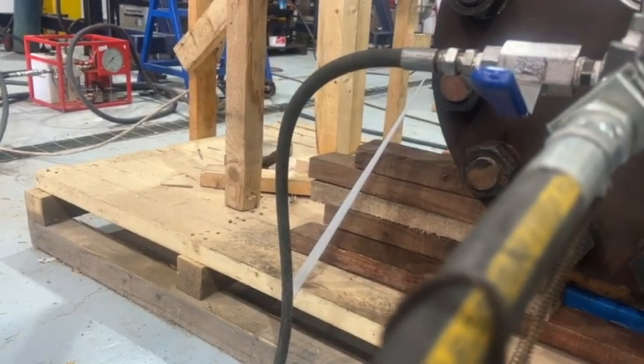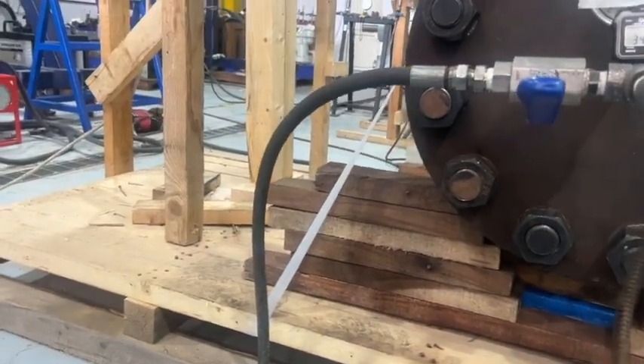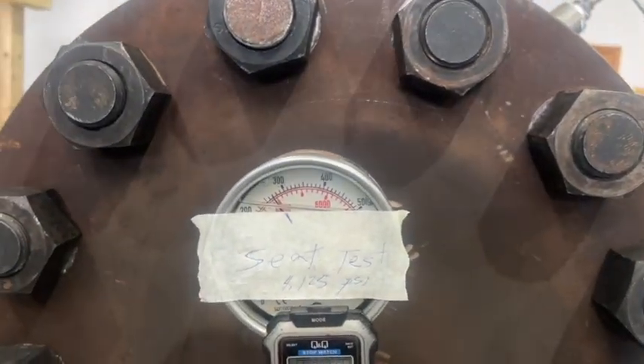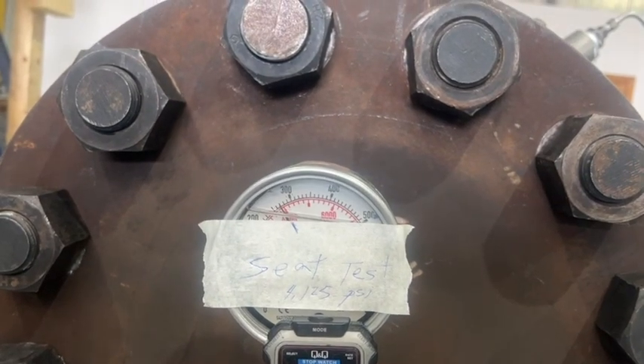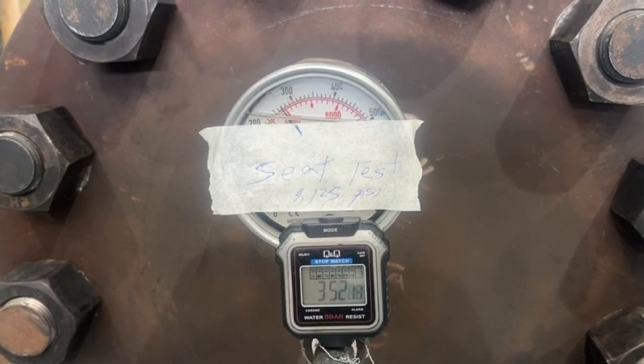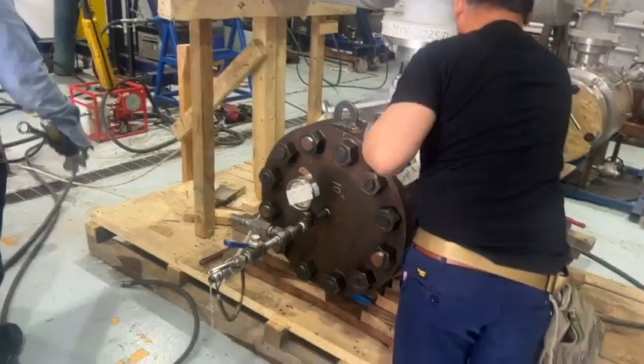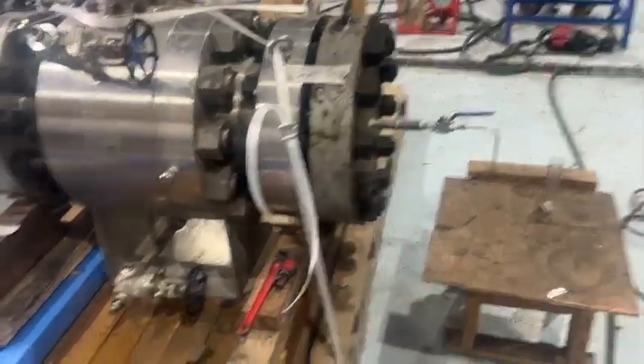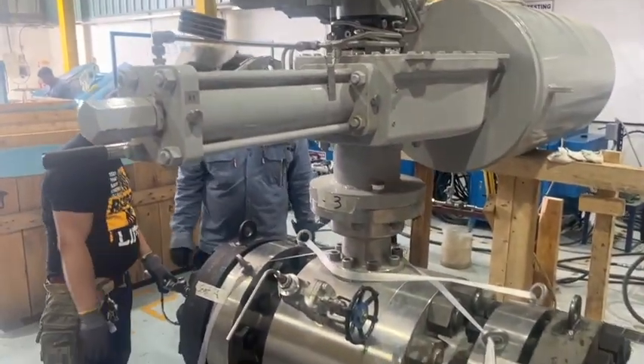It is losing pressure — oh no, it loses the pressure, but we can say we accept that. Side A seat test is accepted as per the criteria. Now they release the pressure again and will install the seat setup on this side, then we will test seat B, and hopefully we get the valve cleared today.